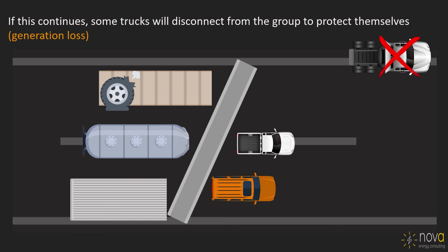So what happens when one of the trailers has to push or pull too hard? They have their own protection mechanism. If they can't sustain the pull of the load, they're going to disconnect themselves. So rather than disconnecting the load, we disconnect the generator. That saves the generator, but it makes the grid weaker on that spot. What that means is then that load is going to have to be shared by the remaining generators on the system and try to compensate and bring back stability.